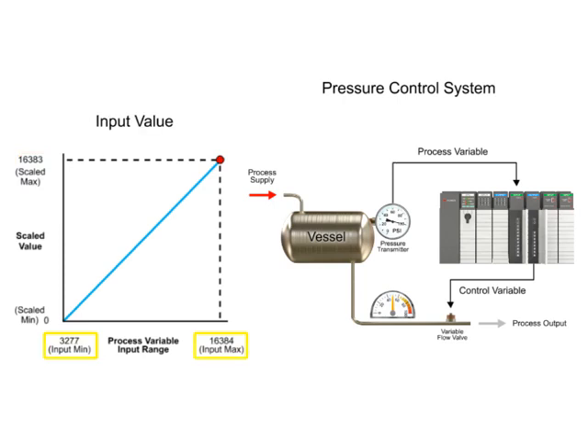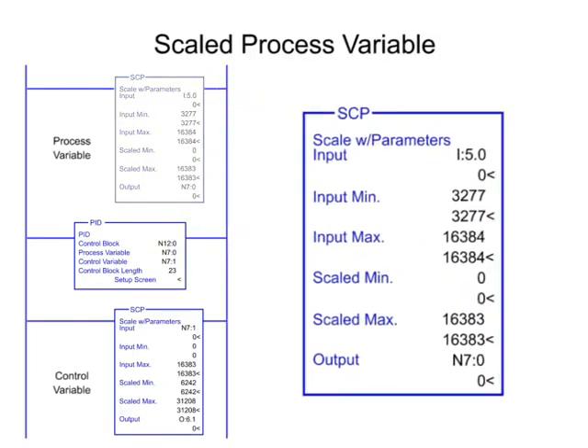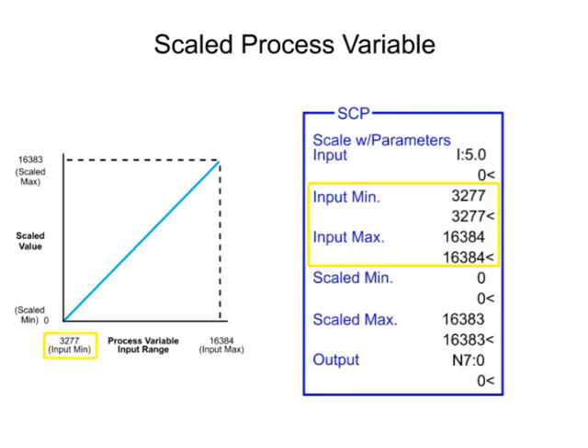The input value is scaled to a range of 0 to 16,383 compatible with the PID instruction using the Scale with Parameters instruction, or SCP. The input parameter of the SCP instruction contains the memory address of the analog input module. The input minimum and input maximum are programmed as the smallest and largest values produced by the analog input module. The input values are then scaled between the ranges programmed in the Scaled minimum and Scaled maximum parameters. Scaled minimum value is programmed as 0, representing the low end of the output range. Scaled maximum value is programmed as 16,383, representing the high end of the output range.